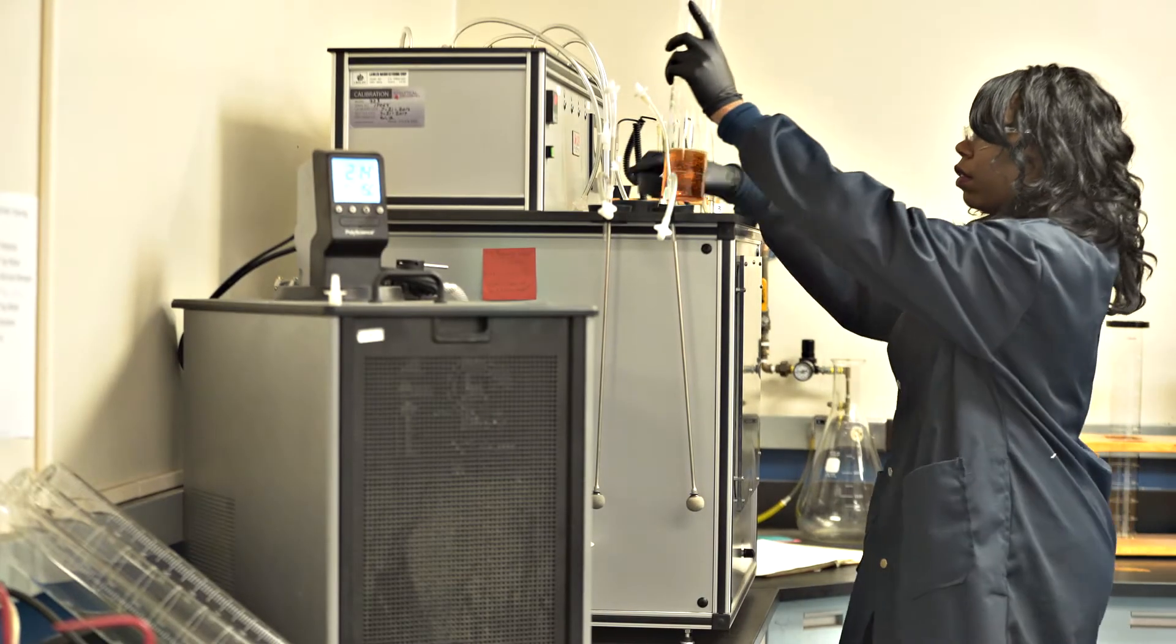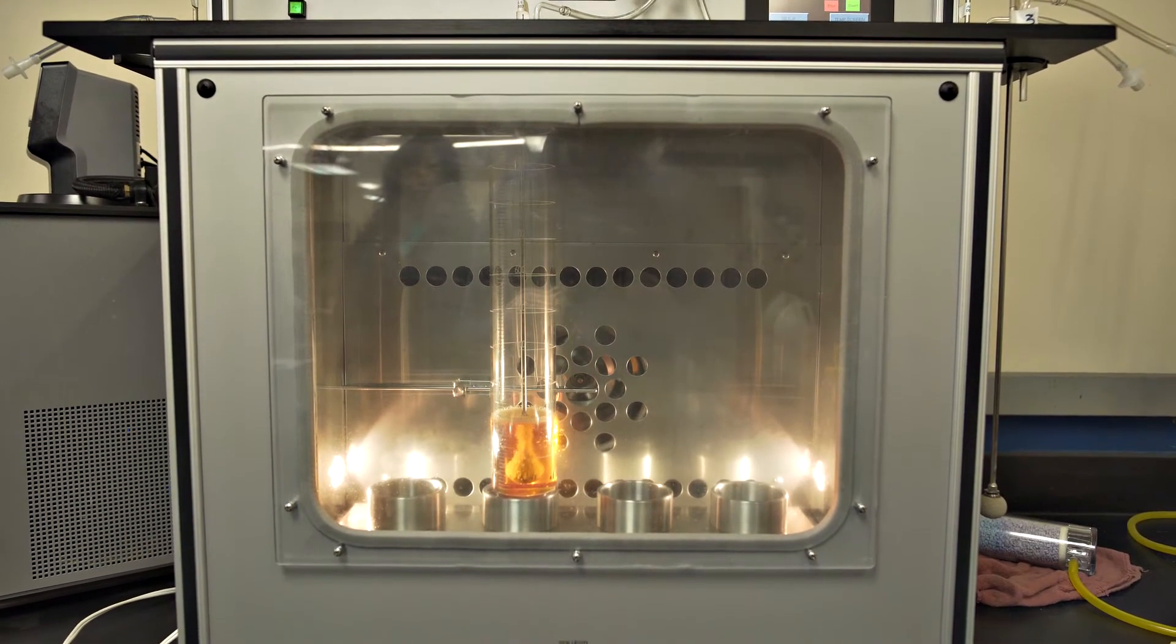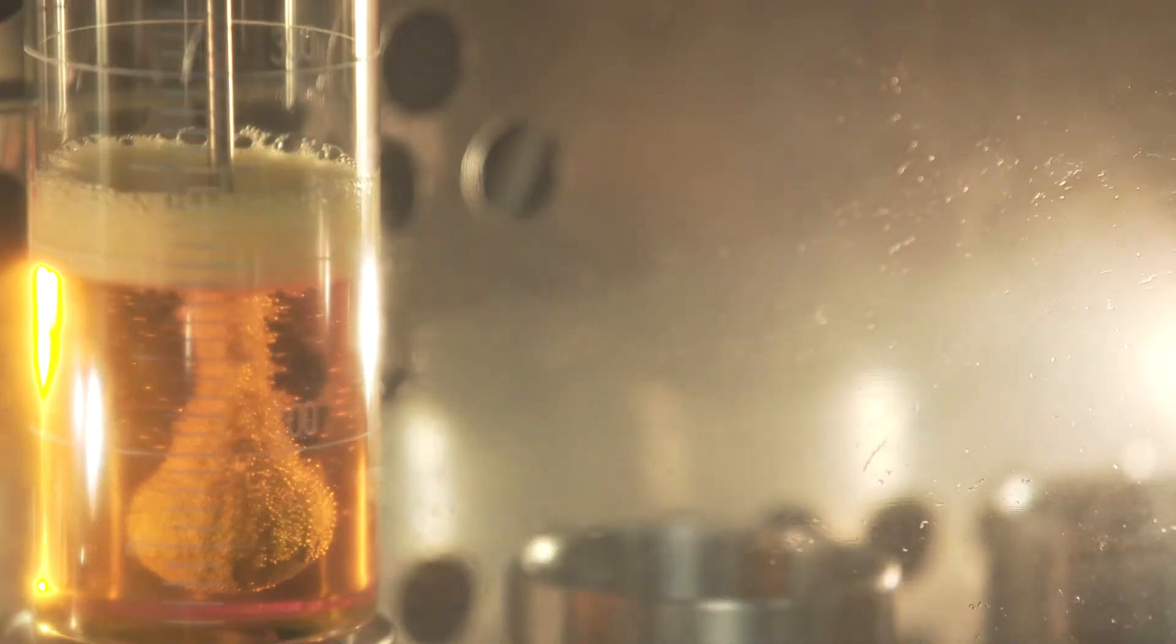Foaming tendency and stability is tested to ensure the turbine oil in service is not prone to excessive foaming, which reduces the circulation flow and fluid film protection on moving parts.